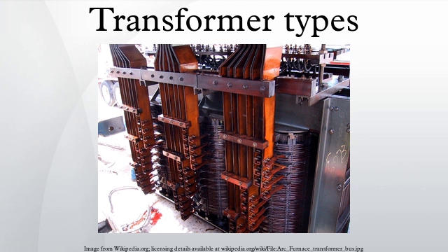Oil-cooled transformer. For large transformers used in power distribution or electrical substations, the core and coils of the transformer are immersed in oil which cools and insulates. Oil circulates through ducts in the coil and around the coil and core assembly, moved by convection. The oil is cooled by the outside of the tank in small ratings, and in larger ratings an air-cooled radiator is used. Where a higher rating is required, or where the transformer is used in a building or underground, oil pumps are used to circulate the oil and an oil-to-water heat exchanger may also be used.